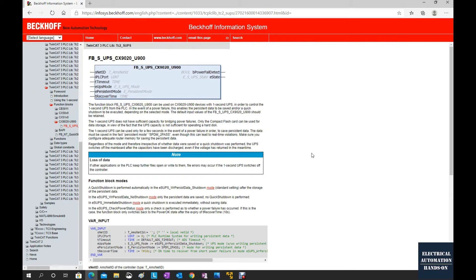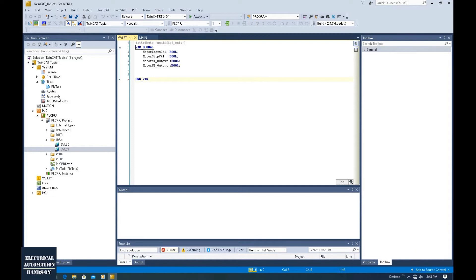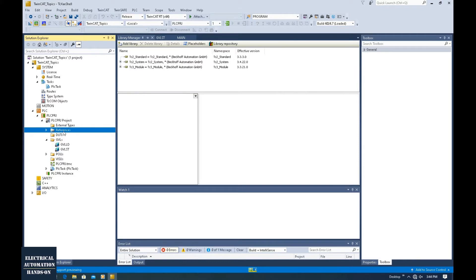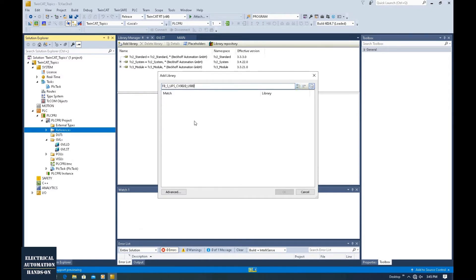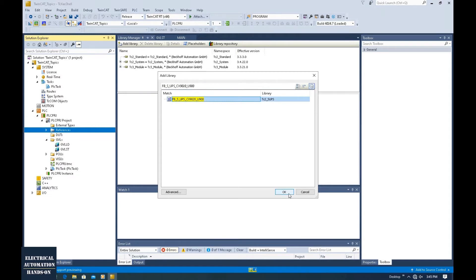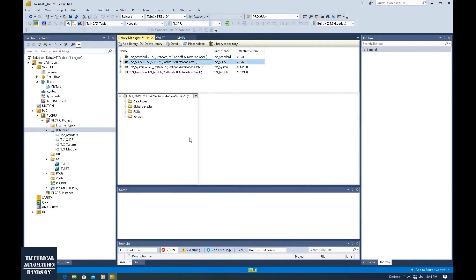Let me show how we can program that. This is a TwinCAT 3 project. To find where we can call that function block, we need to go to References under the PLC project, right-click, and add a library. That is a system library. Let's type in the name: FB_S_UPS_CX9020_U900. You need to wait a couple of seconds to allow the system to search this function block. Once found, click OK and it will be added to your project.